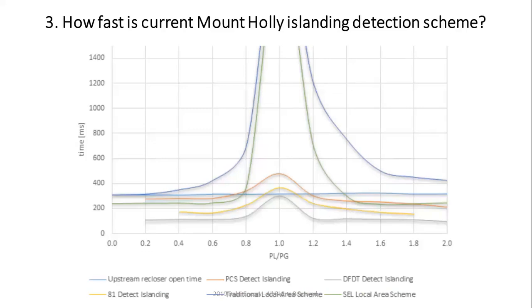Just to let you know, I have a bunch of slides over here. You can probably see the settings for each one of those. But the scheme that we have over here has been tested several times. We tested in different temperature conditions, when it's really hot, when it's really cold, and these are the results that we received. Now I do have to tell you, sometimes you can see the numbers over here on the left. These numbers were actually tested with us opening the point of interconnection. So I showed you we have a point of interconnection, which is a recloser upstream. They can also simulate a breaker or something like that. We would actually open that.